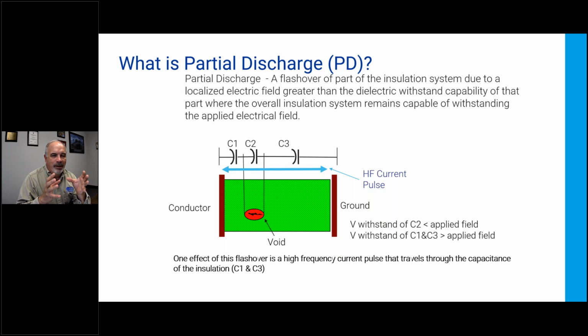balance everything out. And in order to change the voltage on a capacitor, if we remember back to freshman year of college, we would flow current through it. And so partial discharge is a current pulse that is a result of a voltage flashover. And that's important to remember. We'll talk later about this current pulse and what we do about it. But that's the nature of partial discharge. It's not voodoo. It's not smoke and mirrors. It's a current pulse as a result of a voltage collapse.